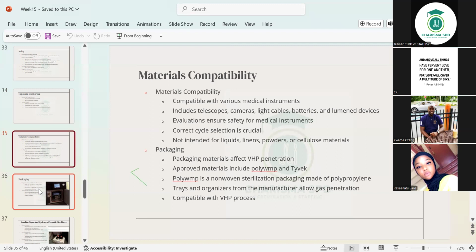Correct cycle selection is also crucial. All right? Not intended for liquids, linens, powders, or cellulose materials. The packaging materials, the way you package it, affects sterilization. No matter what machine you are using, your packaging is going to affect sterilization. So try not to do the wrong thing. We've told you a lot about how to package it. No overcrowding, no overloading. Make sure heavy items go down and the light ones on top of them to ensure that there's complete penetration and exposure.